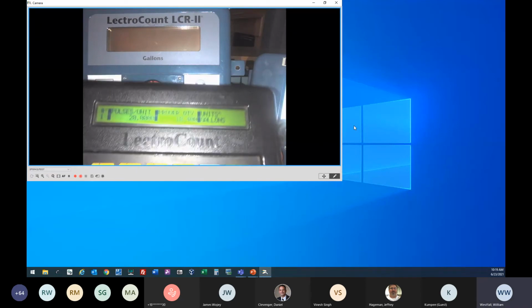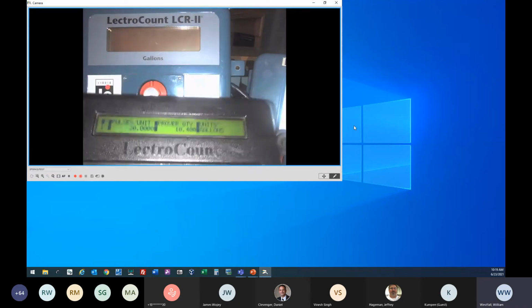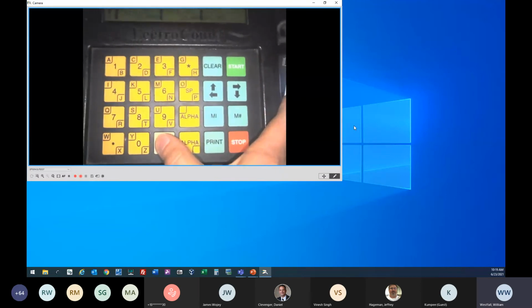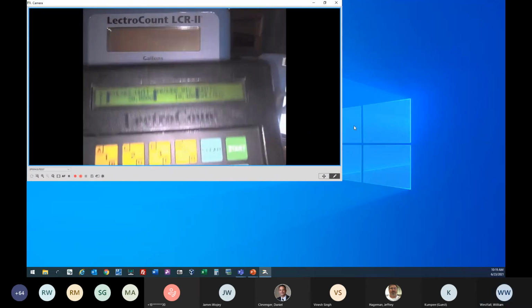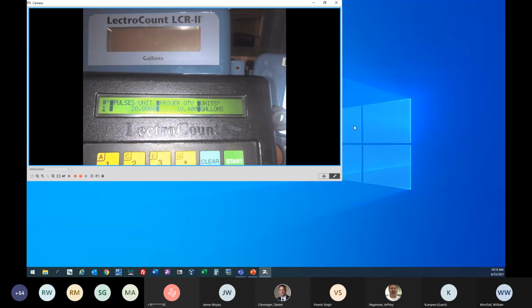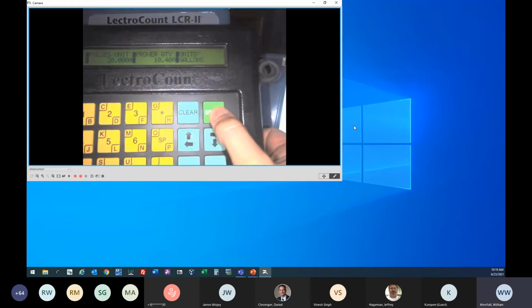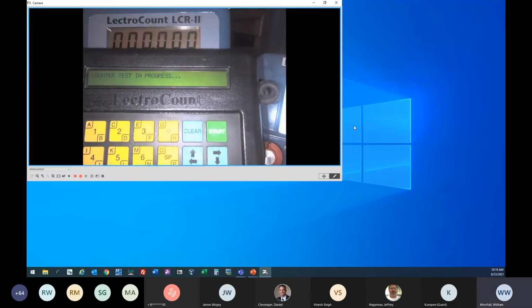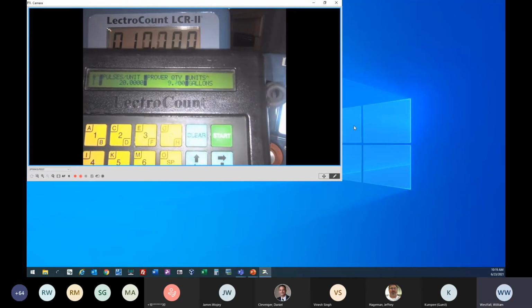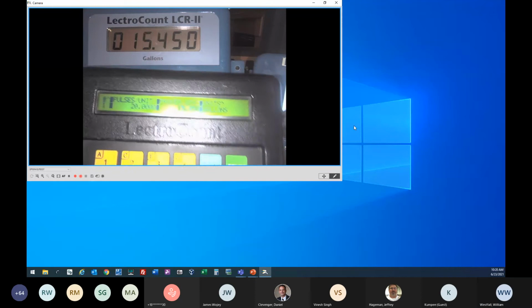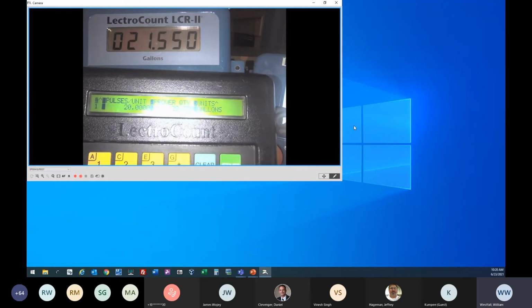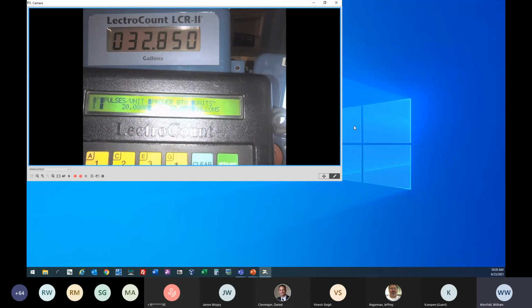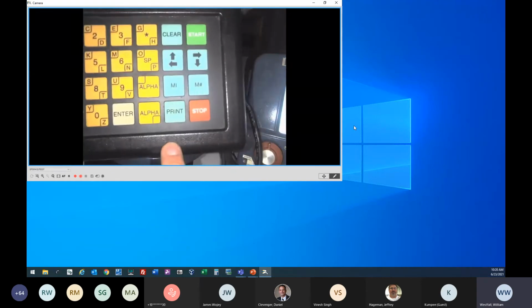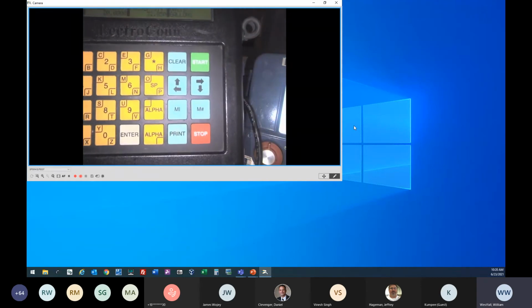And in order to start a calibration delivery with the red knob in that 6 o'clock position, all we have to do is hit the start key. Oops, sorry, not the enter key, the start key. And we should get a counter test in progress. And now we'll fill up our prover. Let's say our prover in this case is only 25 gallons. When we get to the end, we want to hit the print key. The print key is down here. This is how we end our calibration delivery.